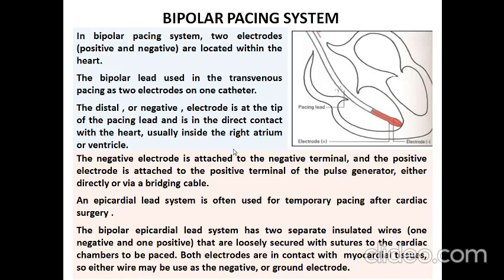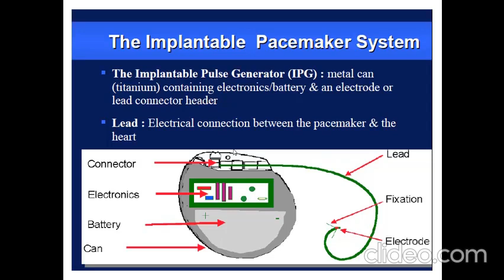Now let us see the concept of an implantable pacemaker system, which is about the IPG. It is a metal can made of titanium containing the electronics, the battery, and an electrode or lead connector header. The leads are useful to make the electrical connection between the pacemaker and the heart. This is a very simple diagram of an implantable pacemaker system.